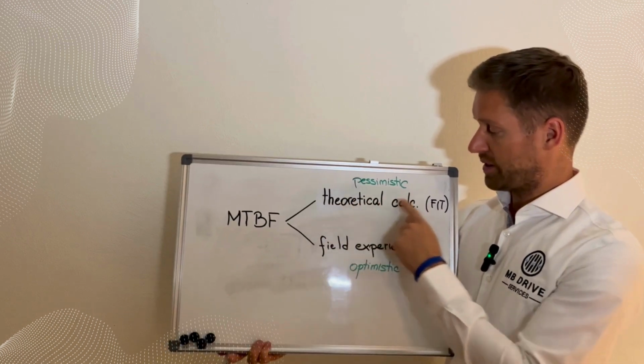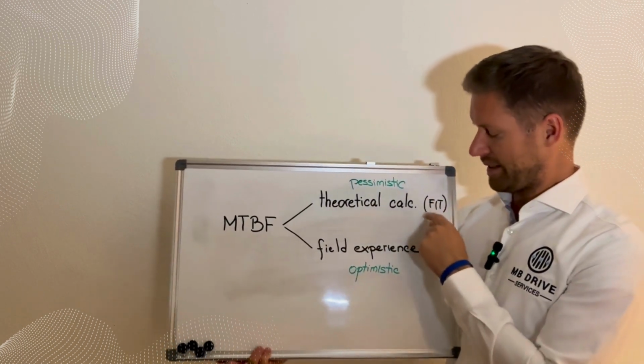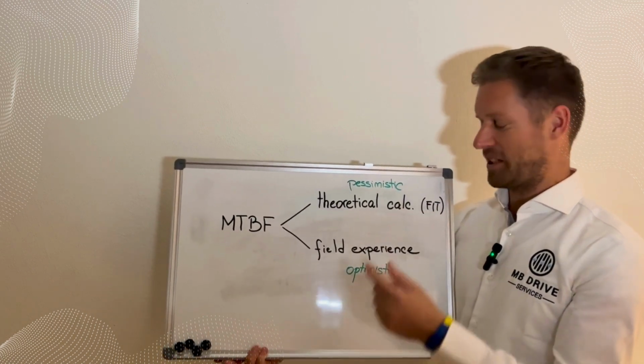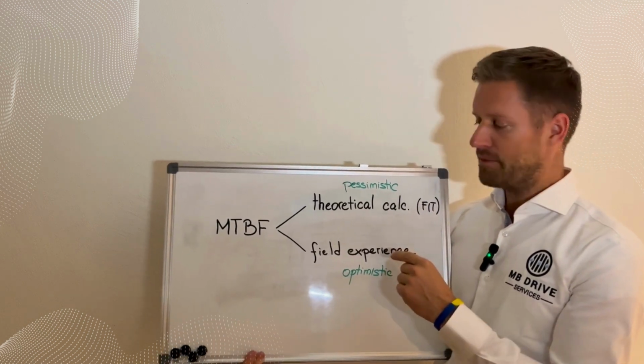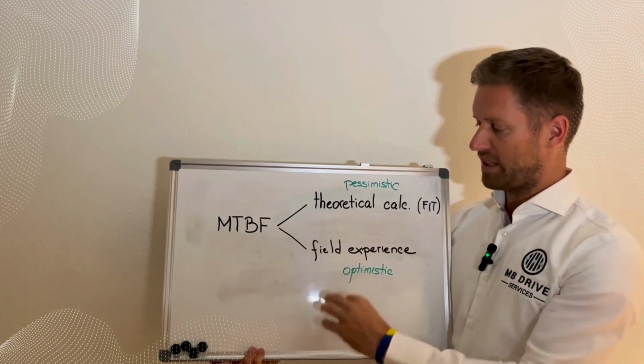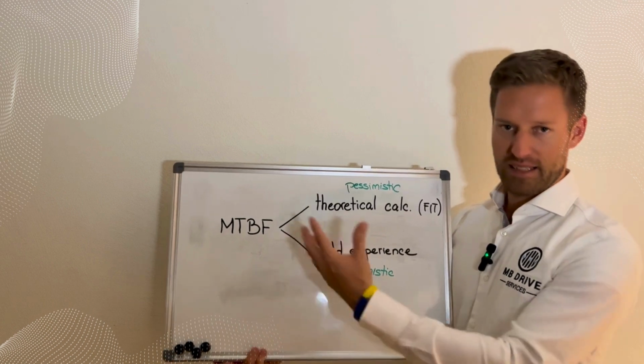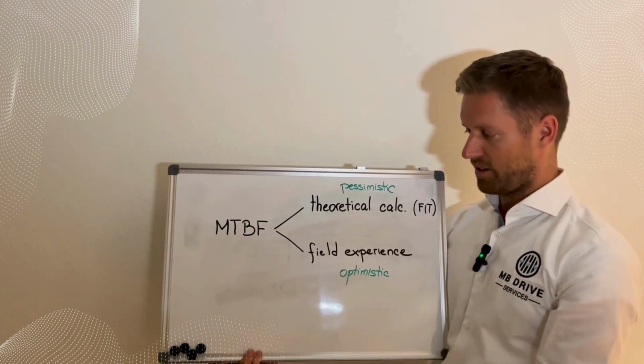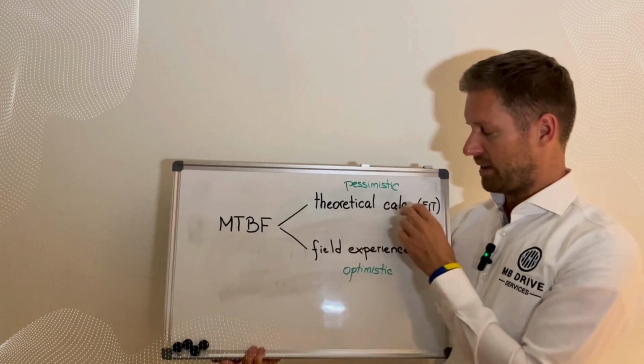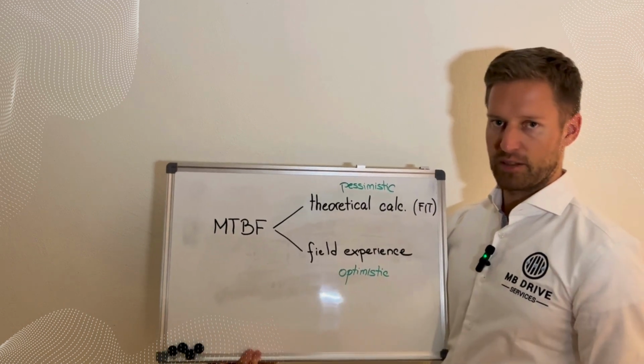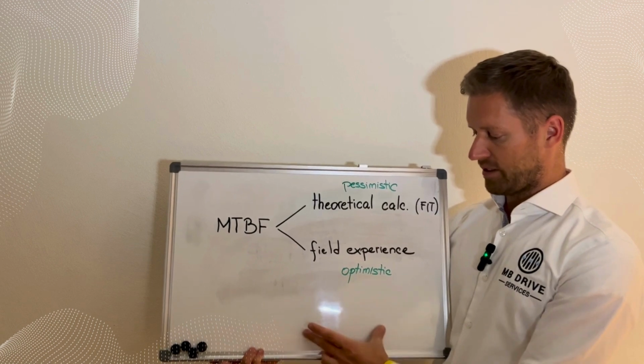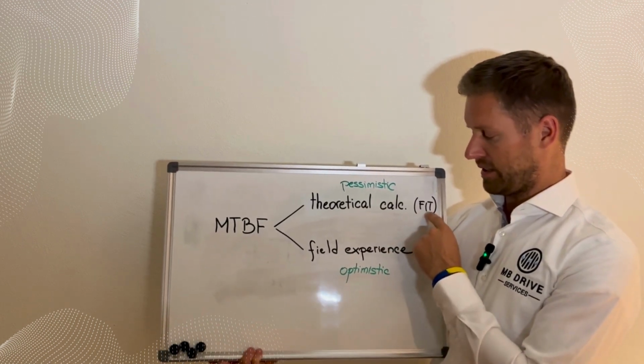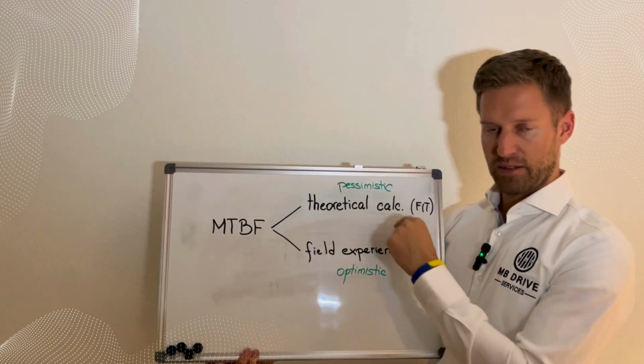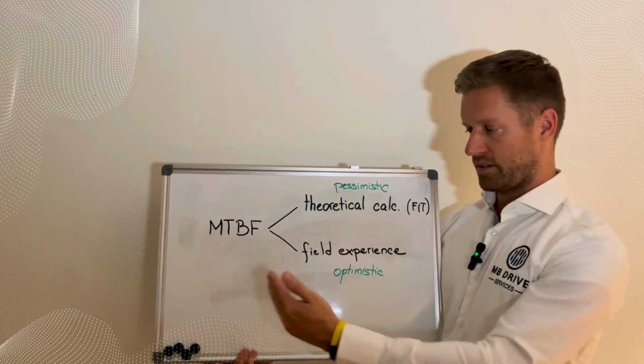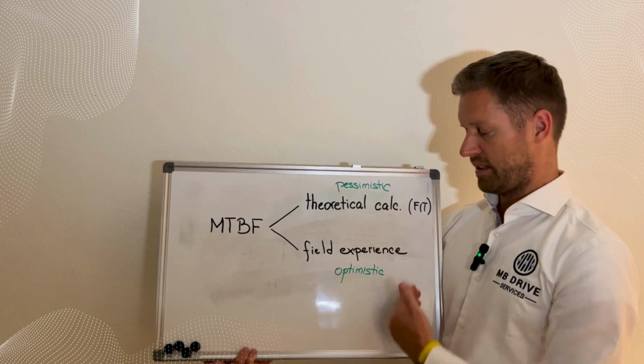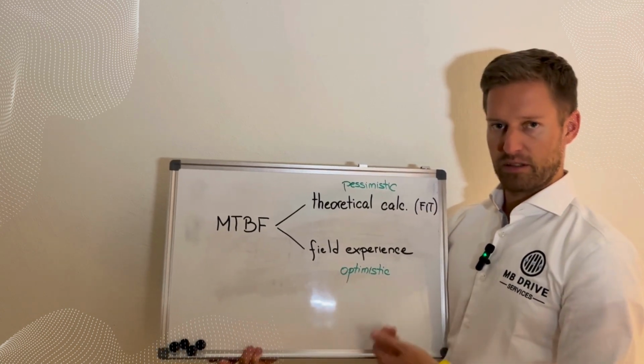One way is to use a theoretical calculation. I put here in brackets FIT. It doesn't mean how fit the equipment is, but FIT means failure in time. For each subcomponent inside the main component, let's say inside the VFD, you have all the parts, and each part has a certain failure in time. This is the number of failures within a certain period of time, by definition 10 to the power of 9 operating hours, so 1 billion hours, and how many failures happen within this period of 1 billion hours.